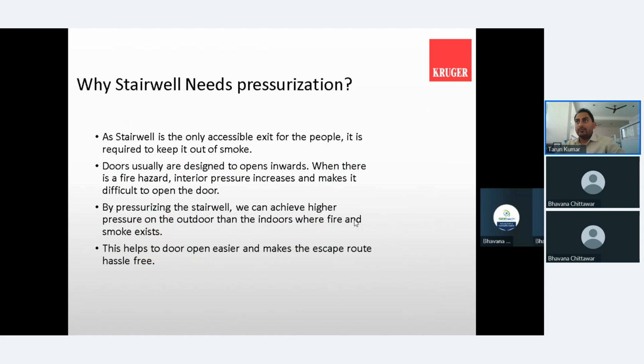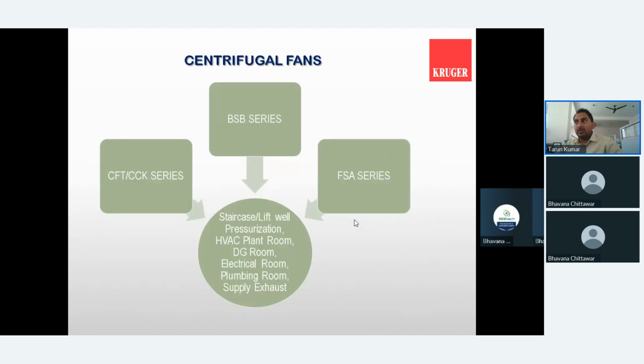That is again backward curve, forward curve, which will basically be defined as per your air volume and static pressure. Here again we are recommending a pressurization fan for staircases, because, as you know, the doors are designed to open inwards into the system. So by that time we use the pressurization fan, and it allows easy opening of the door and bifurcates the fume from the staircase so that people can easily escape.